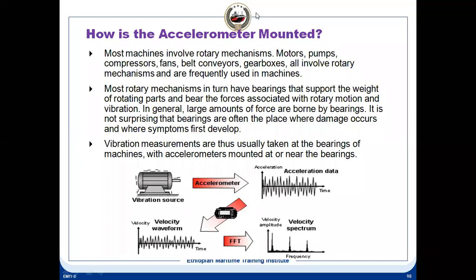This is converted into 4 to 20 milliamps. The output from the vibration sensor is 4 to 20 milliamps. That is given to the PLC unit. So whenever the acceleration exceeds the limits, the PLC will activate the signals to trip these machineries. Vibration measurements are usually taken at the bearings of the machines, like fans. All these places you'll find the sensors. So this is the purpose of the vibration sensor.